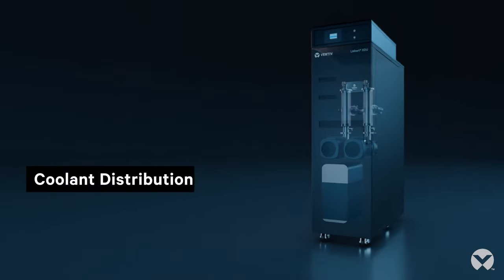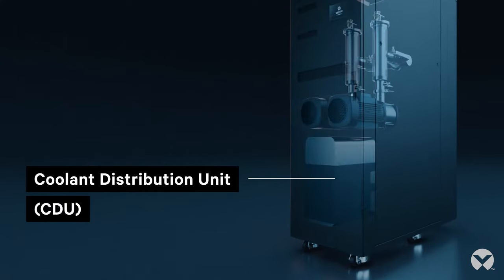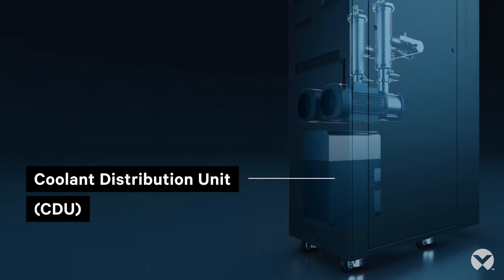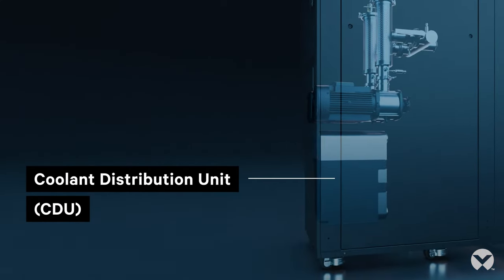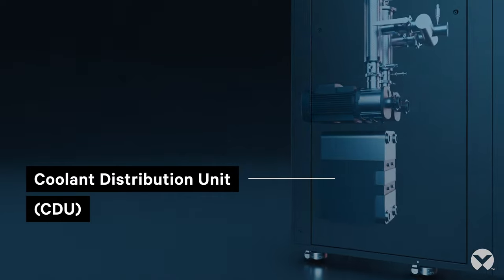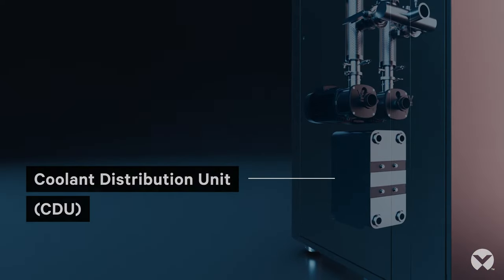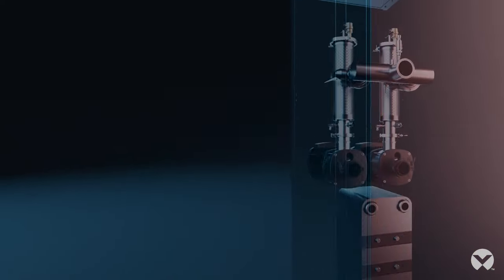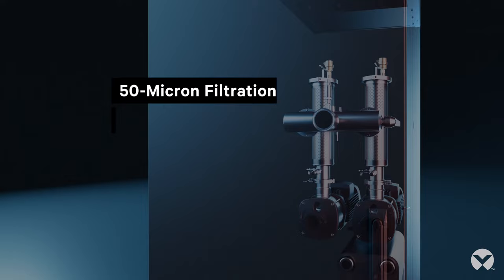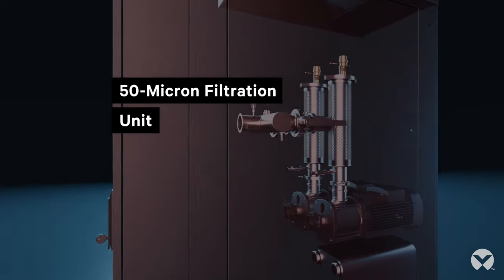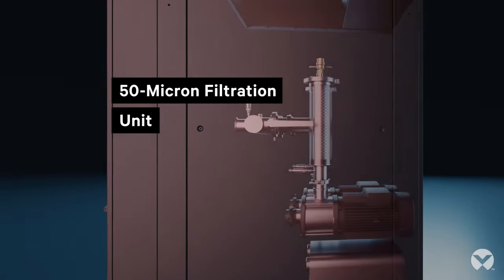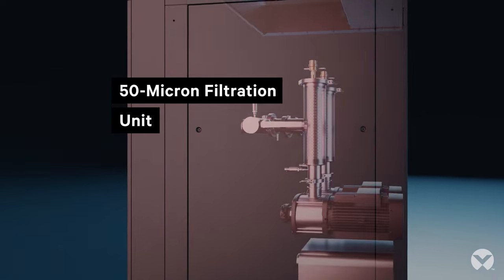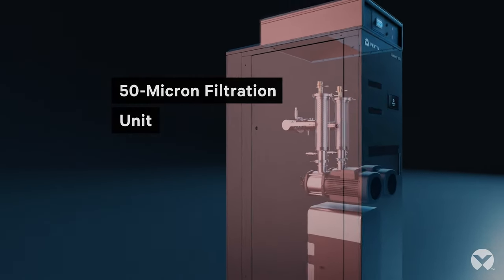Second, the Coolant Distribution Unit or CDU features an innovative stainless steel design to provide essential separation of the primary facility water from the IT heat load, so there's no need to worry about corrosion. Built-in 50 micron filtration units keep the secondary fluid network free from debris and contaminants, ensuring optimal performance of the cold plates and rear doors.